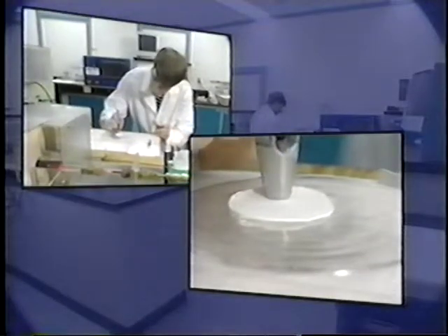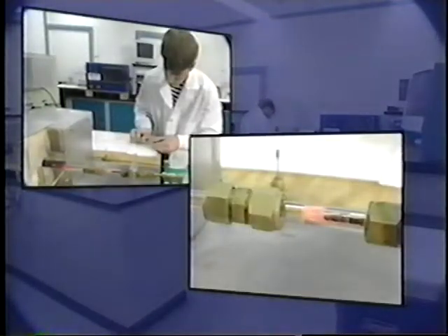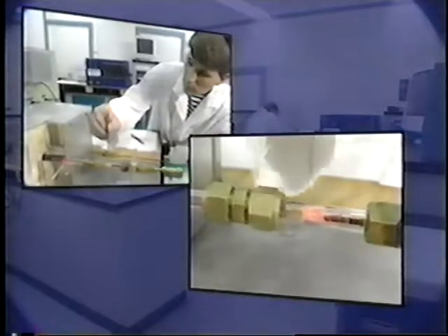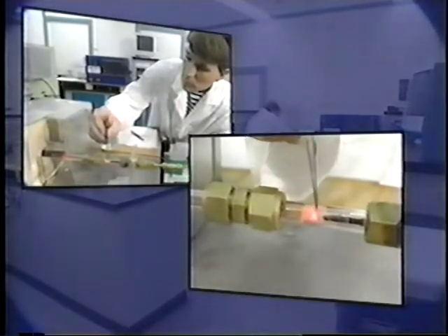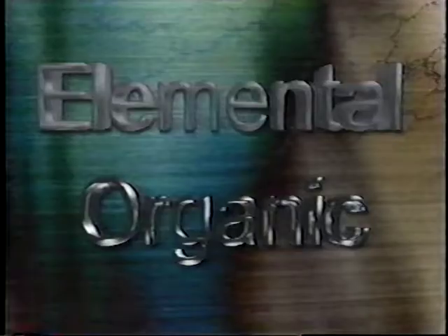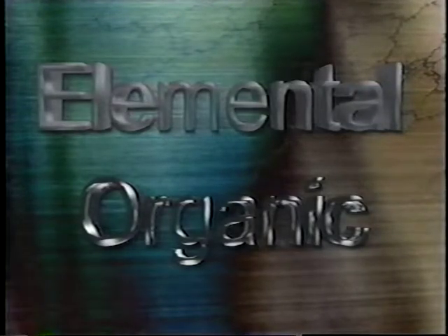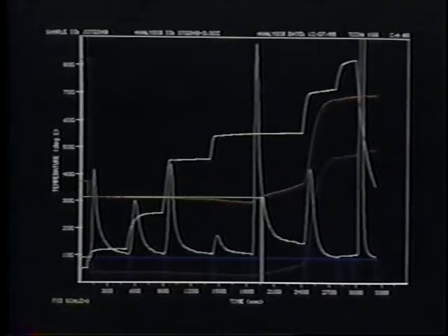The TOR method of carbon analysis utilizes volatilization and combustion to remove light-absorbent carbon while measuring the reflectance from the deposit side of the filter. Temperature is relied upon to distinguish between organic and elemental carbon. In this case, organic carbon is carbon that does not absorb light at the wavelength used, and elemental carbon is light-absorbing carbon.